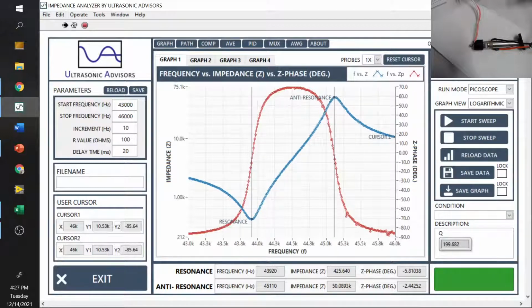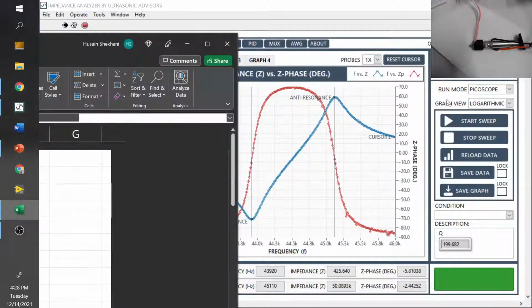So we got to a Q factor of 199. I'm going to log that data. Transducer holder. The Q factor was 199. The impedance was 425 ohms, and the frequency is 43.9. It actually increased 40 hertz, but I'm not going to count that. So let's just take a look at what happened here.